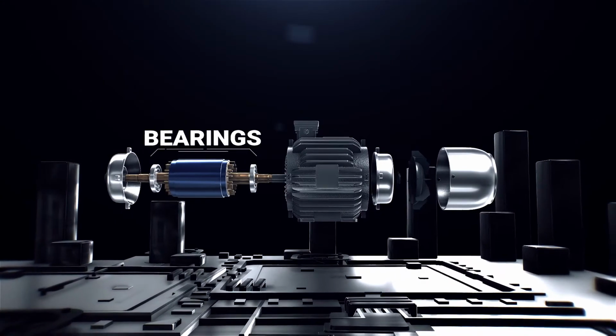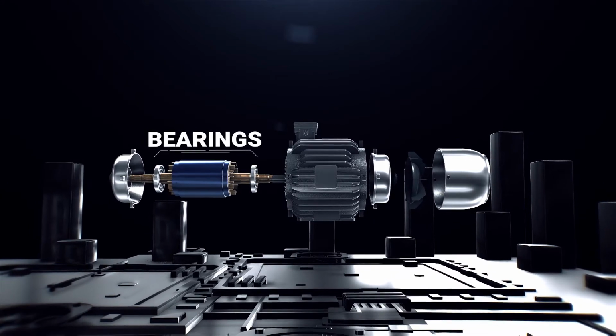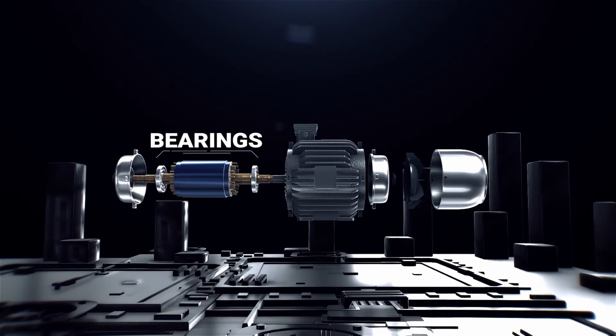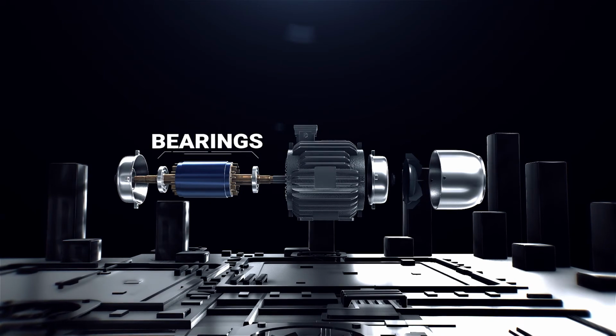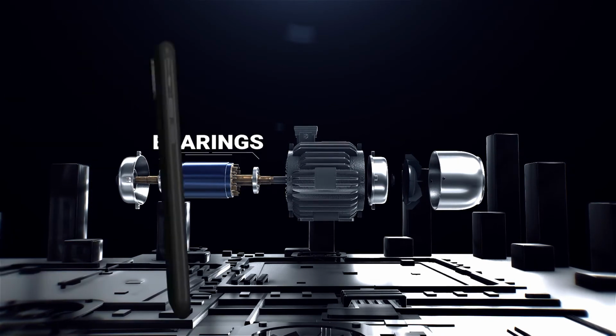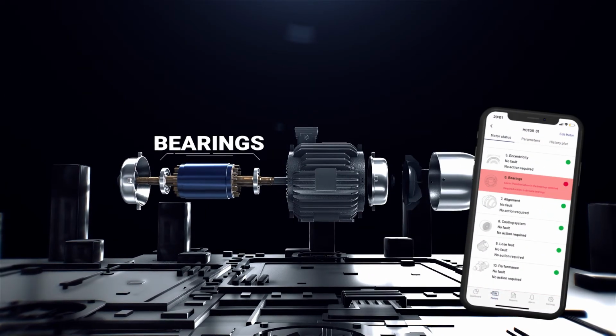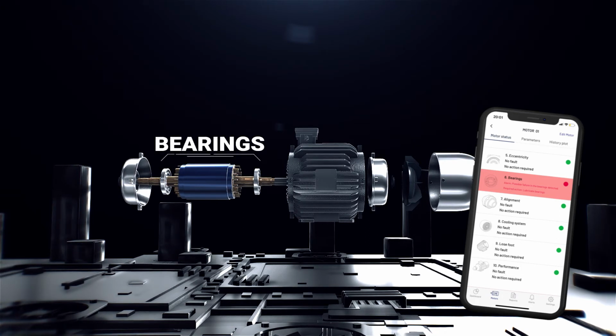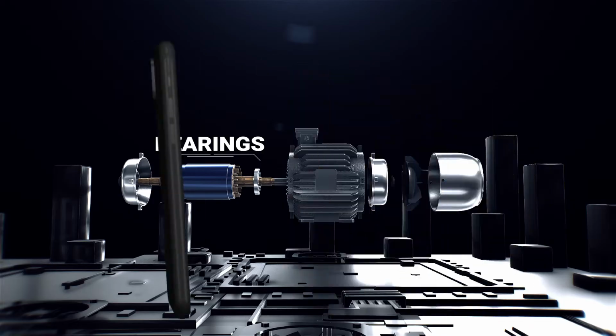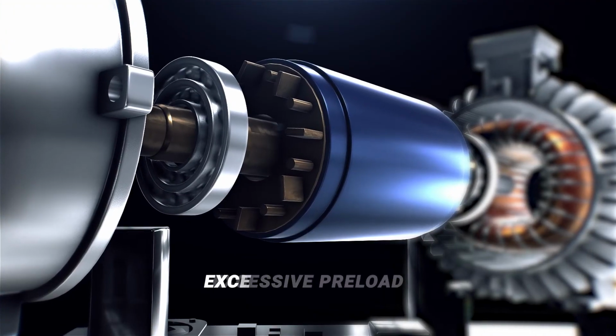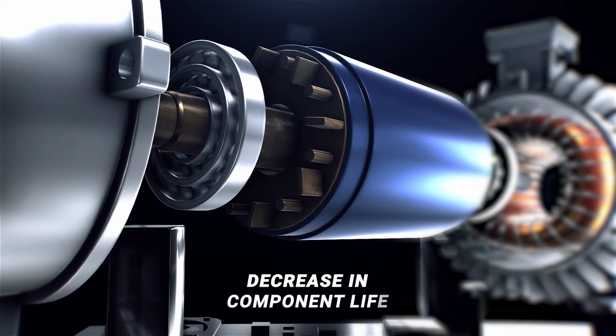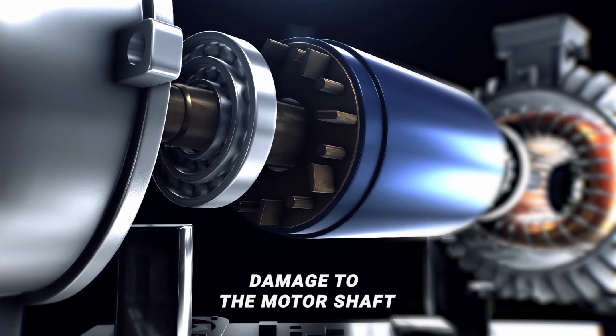Problems with bearings. This mechanical failure occurs due to excessive mechanical tensions, contamination within the component, or incorrect lubrication. This can cause small cracks or defects in the bearing, creating some vibration problems. A bad placement of the bearings may cause failure related to excessive preload, excessive vibration, heating, decreasing component life, damage to the motor shaft.